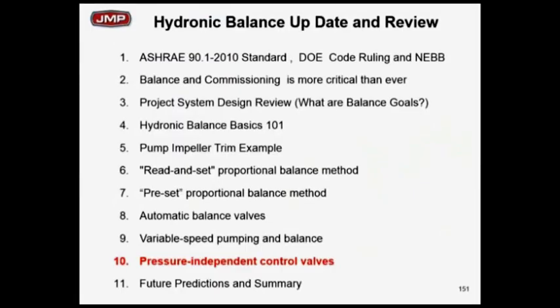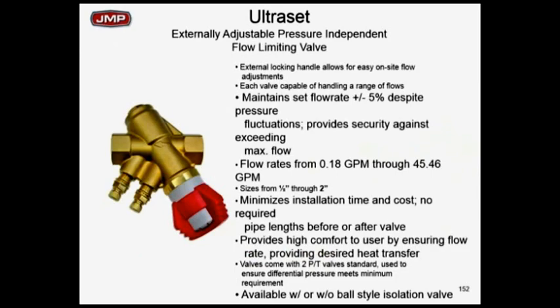Let's look at pressure independent control valves. Now, we can talk products, but basically a pressure independent control valve is one that limits the flow, like a flow limiter, to whatever you've got it set on. Plus, it keeps a constant differential pressure across the two-way valve. Kind of like having two valves in one.